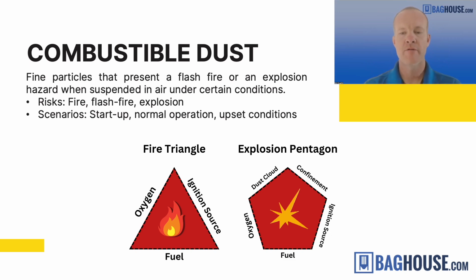When you have that same fuel or sawdust, which is then dispersed, so it's airborne, and then it's confined, so that could be confined in the baghouse or in your ductwork, then you have all five elements for a potential explosion. That's when the NFPA requirements for explosion venting, isolation, spark detection, and extinguishing come in. So it's important that if you have a wood shop, you're aware of your combustible dust being present. You do a dust hazard analysis. You bring in someone who's familiar with NFPA requirements to help you design a system that's going to be compliant and, most important, safe.